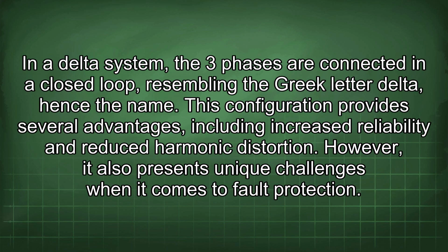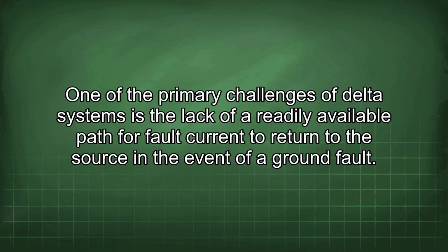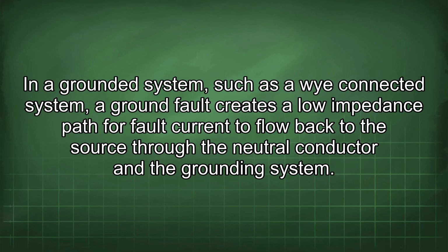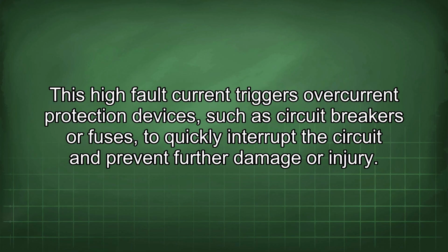In a delta system, the three phases are connected in a closed loop resembling the Greek letter delta, hence the name. This configuration provides several advantages, including increased reliability and reduced harmonic distortion. However, it also presents unique challenges when it comes to fault protection. One of the primary challenges of delta systems is the lack of a readily available path for fault current to return to the source in the event of a ground fault. In a grounded system, such as a Y-connected system, a ground fault creates a low impedance path for fault current to flow back to the source through the neutral conductor and the grounding system. This high fault current triggers overcurrent protection devices, such as circuit breakers or fuses, to quickly interrupt the circuit and prevent further damage or injury.